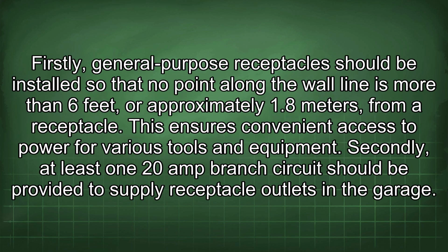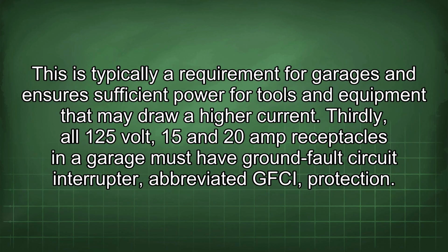Firstly, general-purpose receptacles should be installed so that no point along the wall line is more than 6 feet, or approximately 1.8 meters, from a receptacle. This ensures convenient access to power for various tools and equipment. Secondly, at least one 20-amp branch circuit should be provided to supply receptacle outlets in the garage. This is typically a requirement for garages and ensures sufficient power for tools and equipment that may draw a higher current.